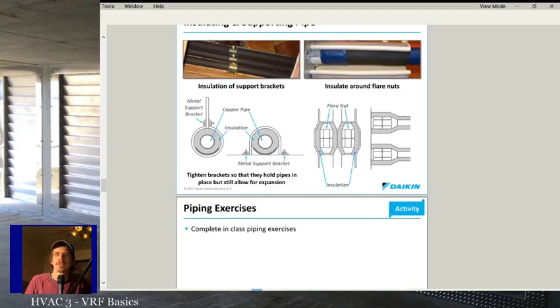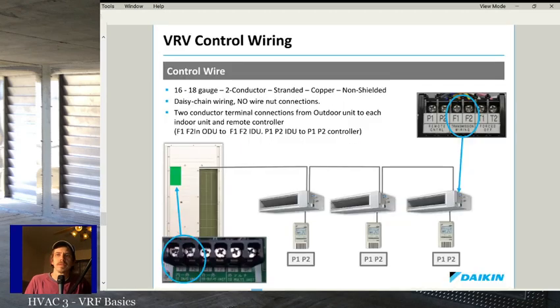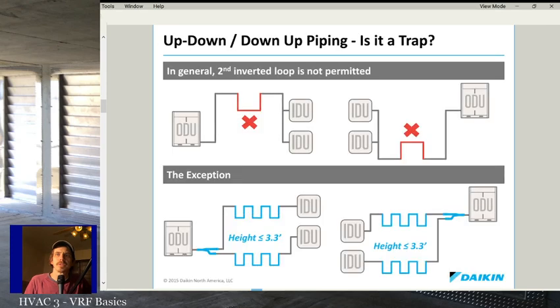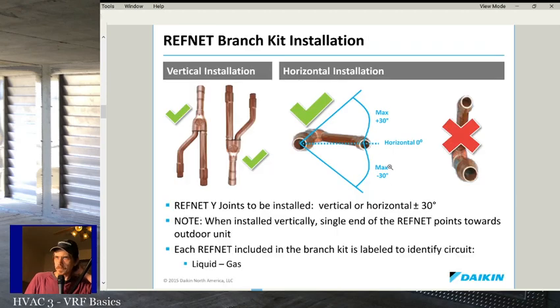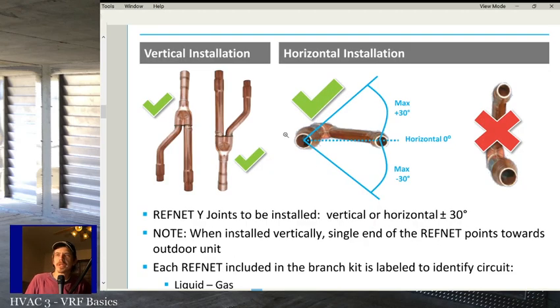is on these Ys. Where's a picture of one of these Ys? On these Ys, they need to be level. And again, this goes back to thinking about refrigerant as a fluid. So when you install a branch kit, and they don't all look like this, but this is what the Daikin ones look like, this should be as level as possible. You can go straight up and straight down. You can go level sideways, but you can't go too far out of level or up and down like this when you split.